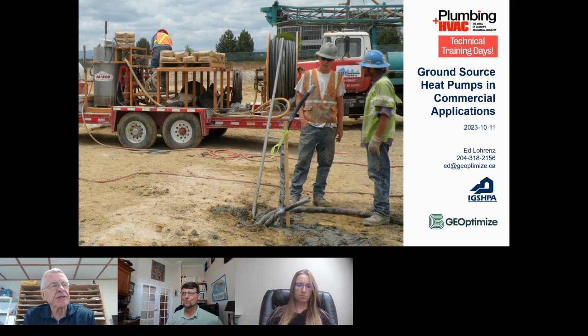Generally, it's not the best thing you could do, because if you're putting a cooling coil with a split system heat pump sitting above a gas furnace, you can potentially get dripping onto the heat exchanger and rot out the heat exchanger on the gas furnace. And the gas furnace typically is going to produce warm air at, depending on how it's sized, probably 110, 120, 130 degrees. That's generally higher temperature than you want to produce with a ground source heat pump. So it's probably not the best idea in the world. And you have to put the gas furnace in ahead of the air coil in most cases, correct me if I'm wrong on that, Greg, but I think that's still the way it is.